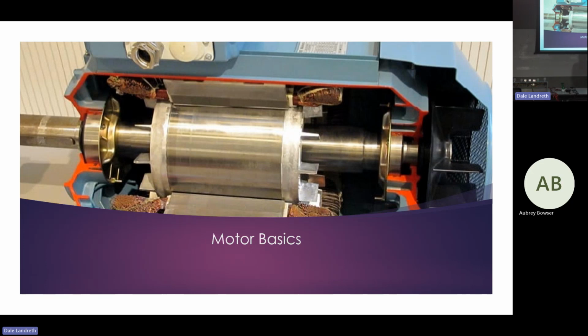Because there's a lot of numbers involved if you want to write this down. So basically the point is we've got to do a mega ohm test and trend it, unless it's just absolutely bad. If I go up there and this motor reads 1 mega ohm, I know the motor's bad, or if it's blowing breakers, I know it's bad. Or if it's still running, which is highly unlikely but possible, I know it's about to go bad.